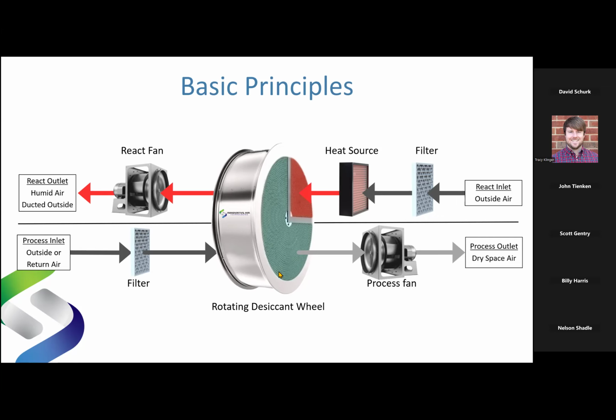So this wheel continuously loads with moisture and revolves into an opposing airstream. One thing I want to point out is that the reactivation airstream, or my drying airstream, or my oven, is a smaller percentage of the total airflow based on the total diameter of the wheel. So what I'm saying is this is about 25% of the wheel's total airflow. If this was a 1,000 CFM wheel, I'd have 750 CFM of process air and about 250 CFM of reactivation air. It's a smaller quantity.